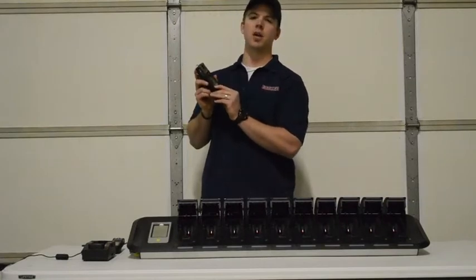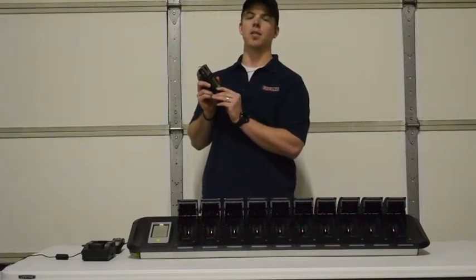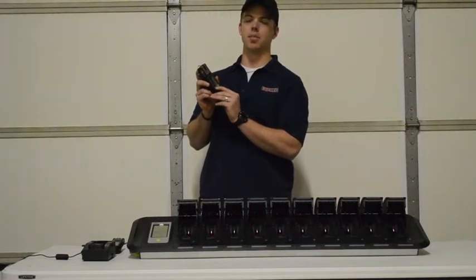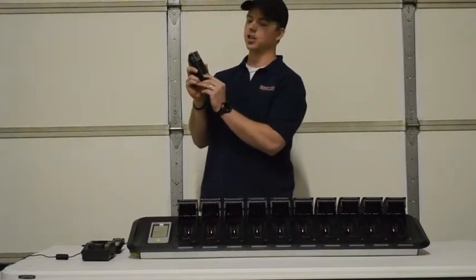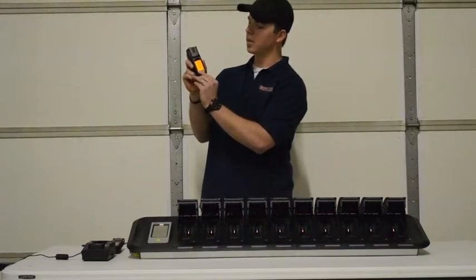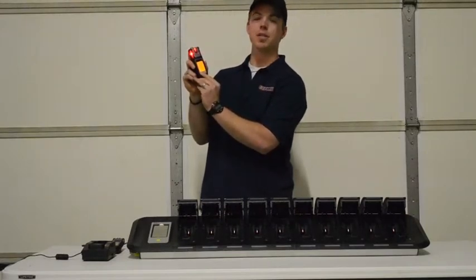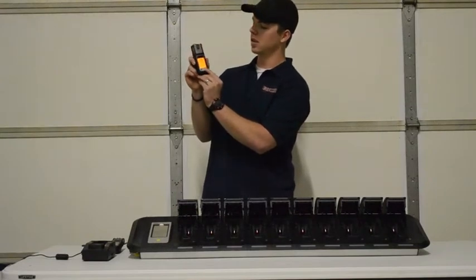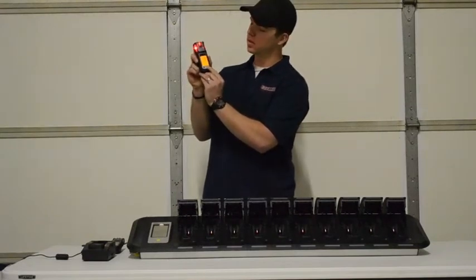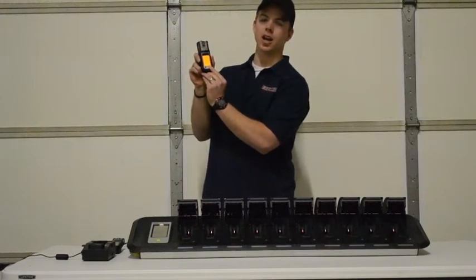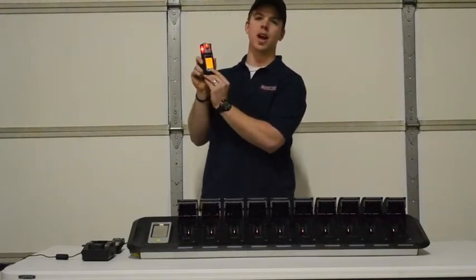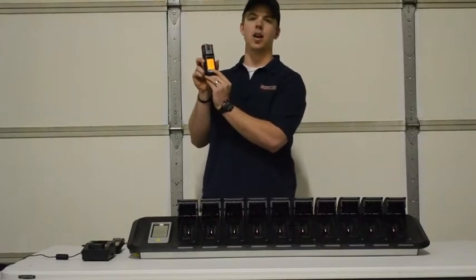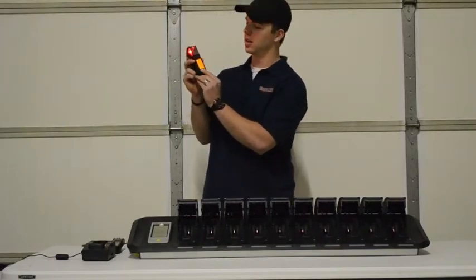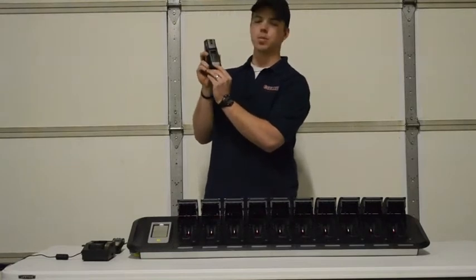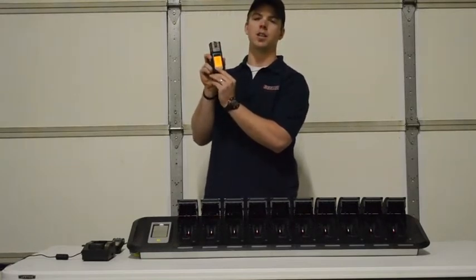So to do a fresh air calibration, go upwind and uphill of any location or outside of a shop. Hit the plus button 3 times slowly. It will bring up a fan looking symbol that says Cal. Hit the OK button once, and then hit OK again. All the sensors will say OK. It will reset all the sensors to 0 and oxygen level to 20.9. To exit this menu, simply press the plus button once, and you're back to the normal reading mode.